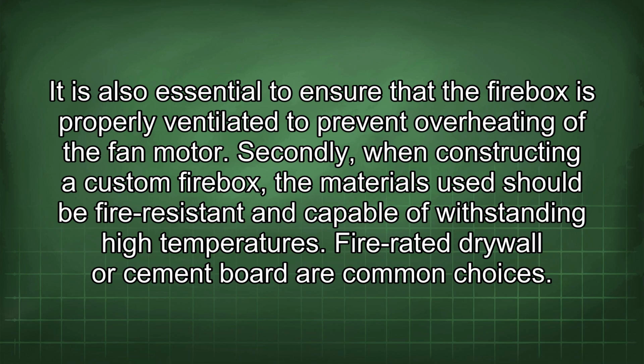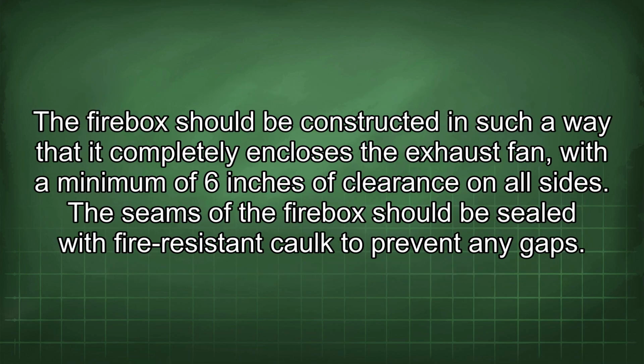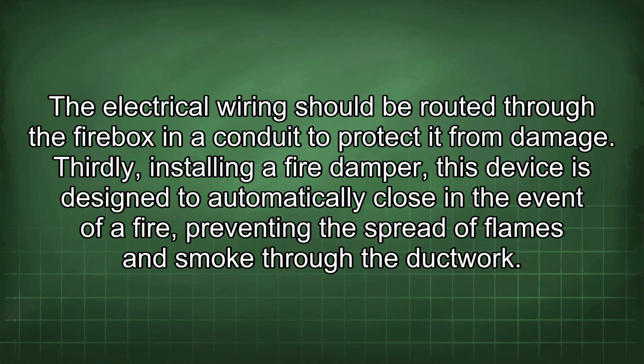Secondly, when constructing a custom firebox, the materials used should be fire-resistant and capable of withstanding high temperatures. Fire-rated drywall or cement board are common choices. The firebox should be constructed in such a way that it completely encloses the exhaust fan, with a minimum of 6 inches of clearance on all sides. The seams of the firebox should be sealed with fire-resistant caulk to prevent any gaps. The electrical wiring should be routed through the firebox in a conduit to protect it from damage.